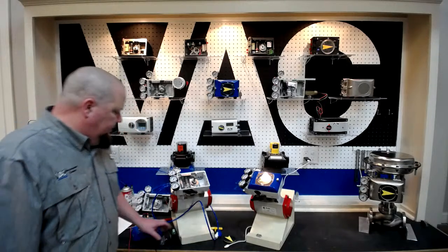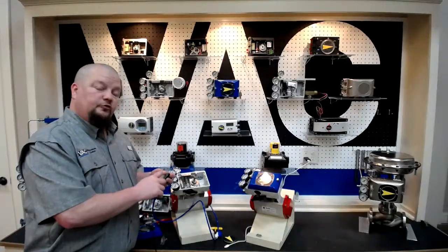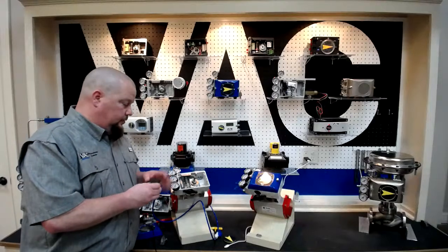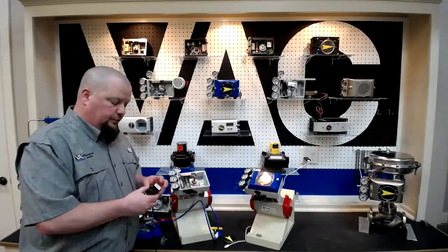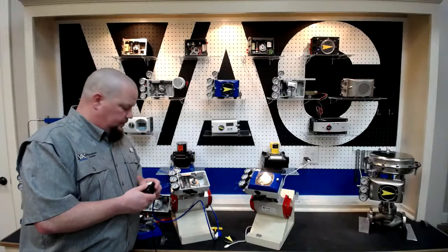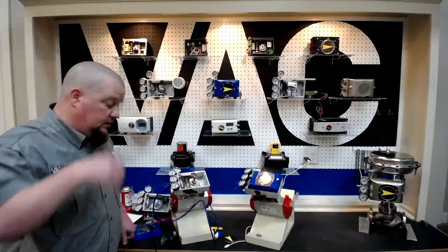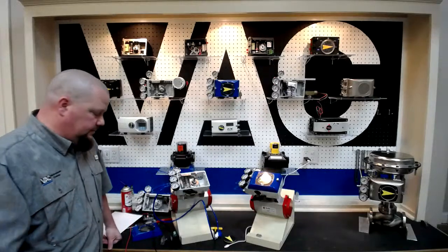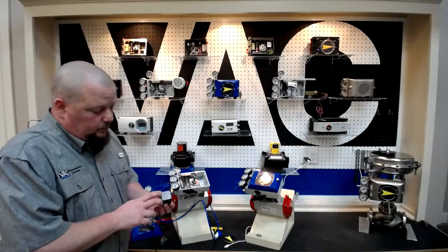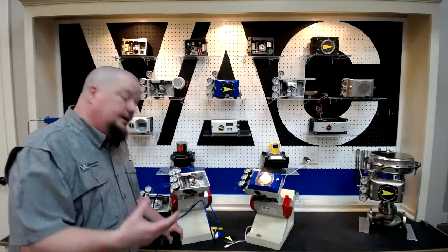Oil is going to be tough. What we have tried in the past is blowing into these filters, and we've had some success bringing back to life positioners that have had a bunch of oil or moisture through them and are stuck. The little air nozzle in there could get something in it, and you might be able to dislodge a piece of trash that way. But that's really it. You can put 60 PSI on a blower and blow in those two ports, and maybe it'll help.